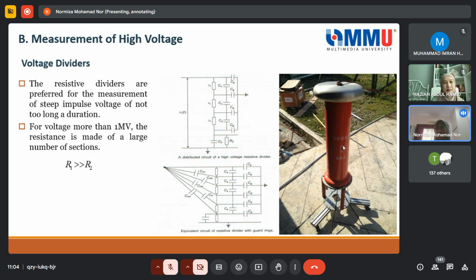This is actually the one that we have at our university that can measure a maximum of 300 kV. So the construction is that on the Z1 it has R1, many R1. We put it into several units. Of course, not me, I mean the manufacturer, they put it into several units. There are reasons for that, because when you have a bigger component, the heat, the losses and everything will be more. We all know that instead of buying one unit, they put it into several units. There are many advantages to that.